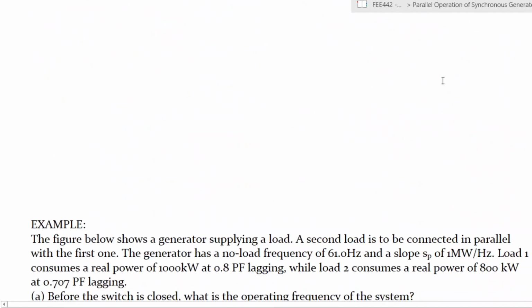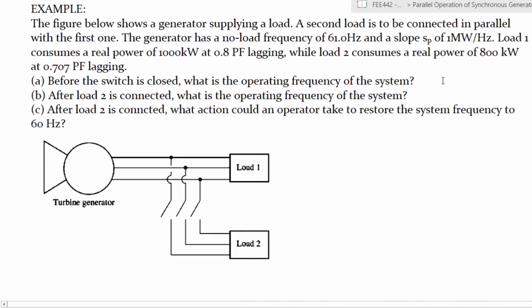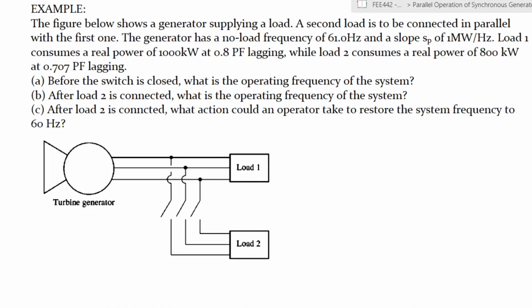Okay, so let's move to do an example. The figure shown shows a generator supplying a load. The second load is connected in parallel to the first one. So here we are not looking at parallel operation, we're just looking at single operation and the changes that will occur to frequency and terminal voltage when we change the load in a generator.